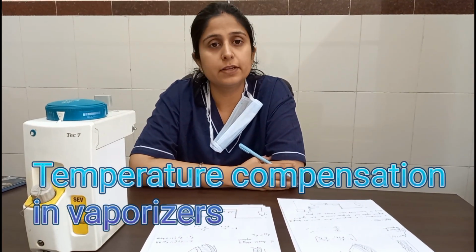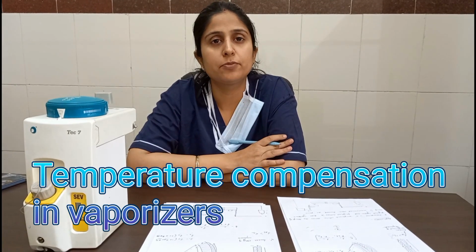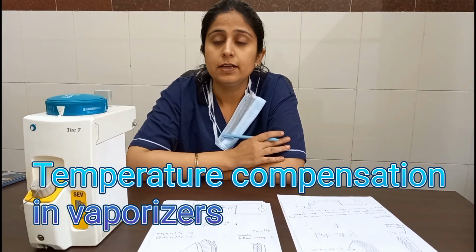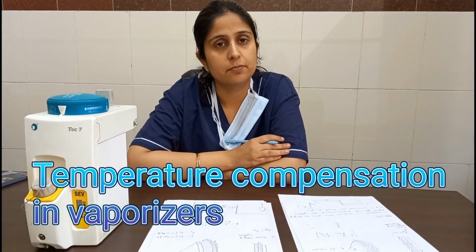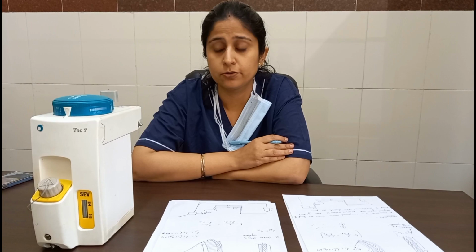Today we will be discussing a very important topic. Daily we are using vaporizers in our operation theatres. These vaporizers are temperature compensated. They are temperature compensated because of two things: one is the bimetallic strip and the other is the aneroid bellows.